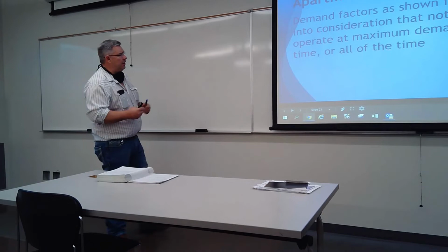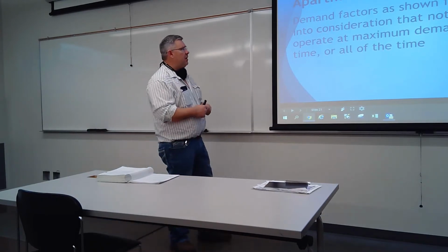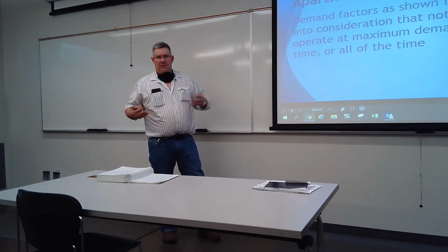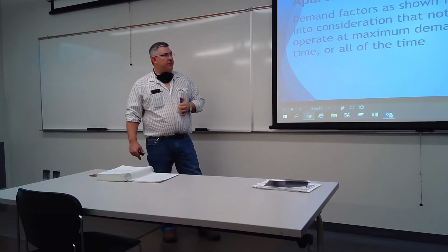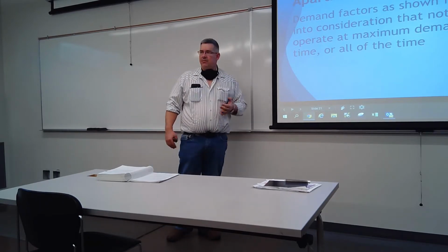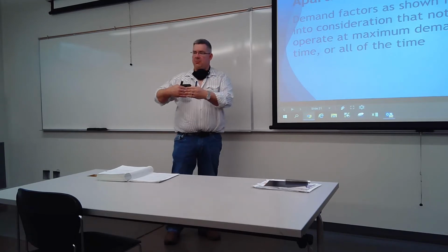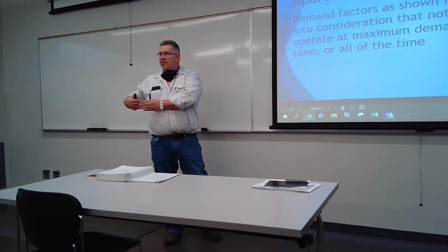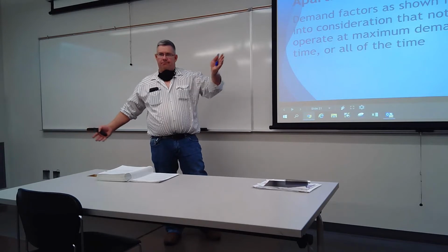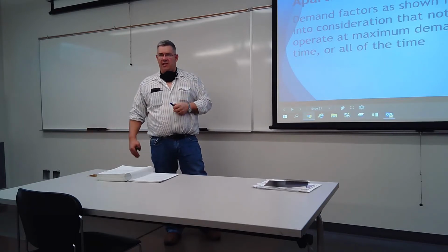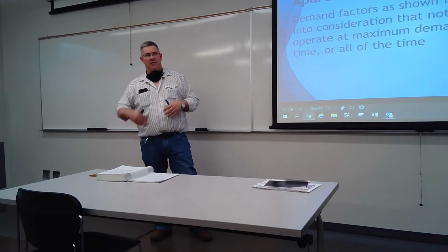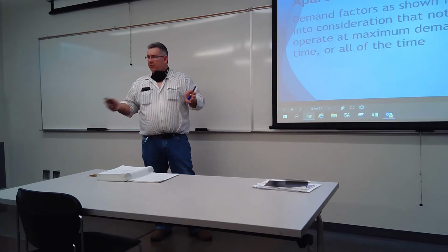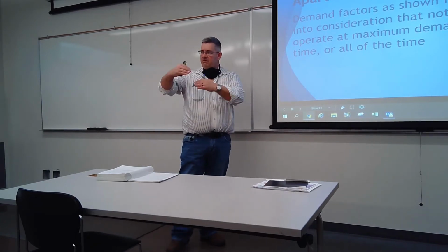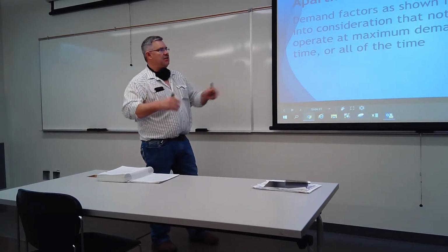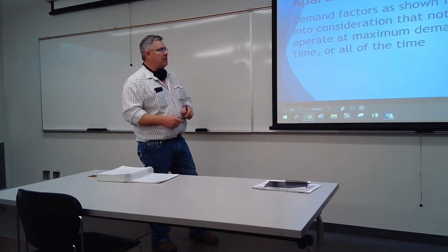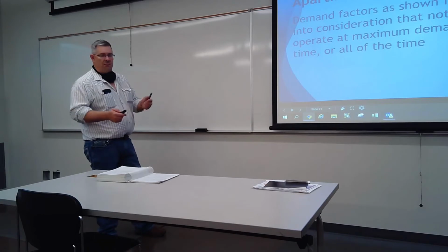And again, when we do the main feeder in an apartment, we break it down because the chances of everybody using all the electricity available in their individual apartment all at the same time is pretty slim. So the more apartments you have, the less those apartments actually contribute to your main demand. Because if you've got a 100-suite apartment building, everybody lives on their own kind of schedule, right? Some people are done work at 4, some are done at 6, some work night shifts. There's people circulating in and out all the time. You don't need as much electrical demand as if everybody was on the same schedule. So the bigger they are, the more apartments there are, the less they actually contribute to your main service.